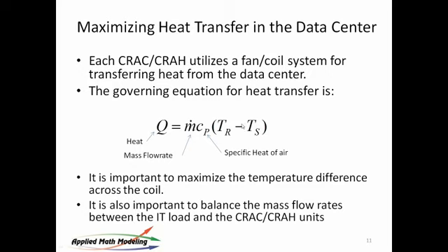Delta T is the return supply difference. So the cooling system and the computers themselves respond to the same equation. They are exactly the same. And you see here we've got a mass flow rate number that's quite important. We'll talk a little bit more about that as we go along. But, of course, the supply and return deltas are important as well.